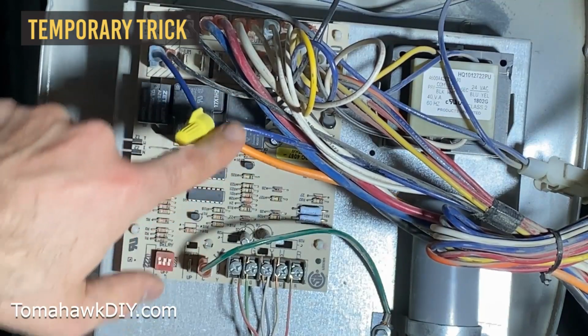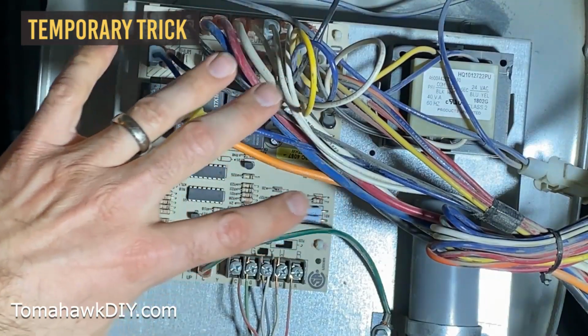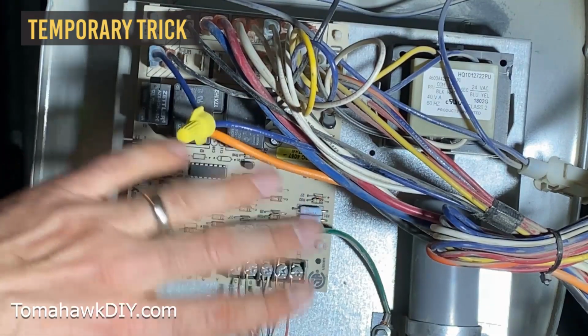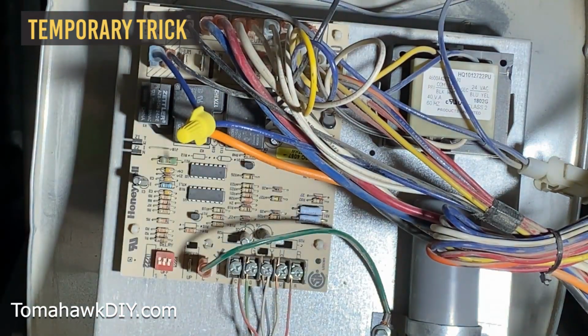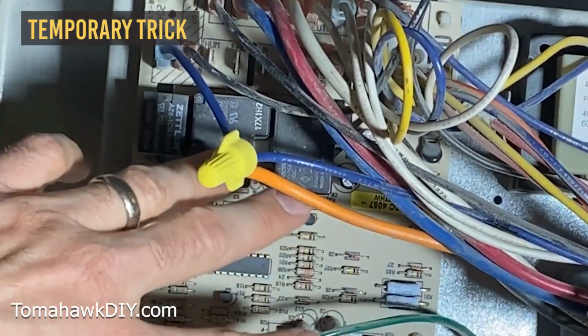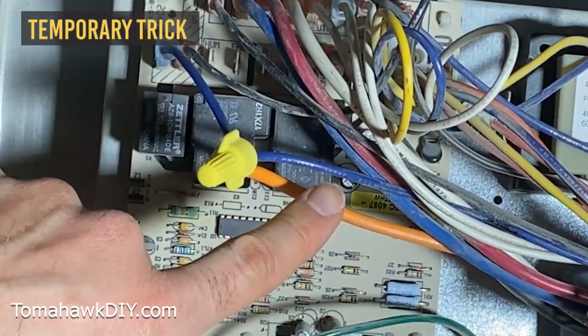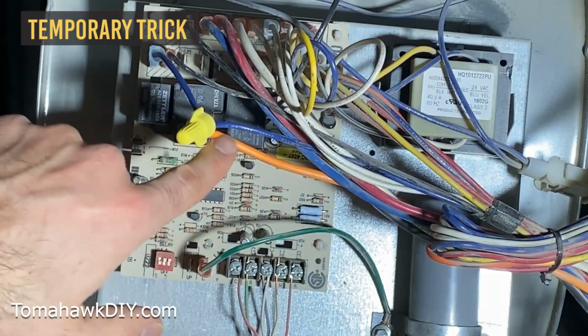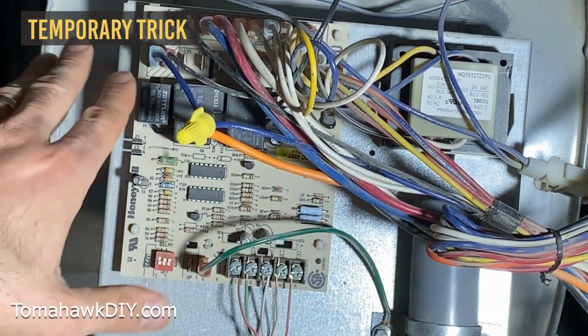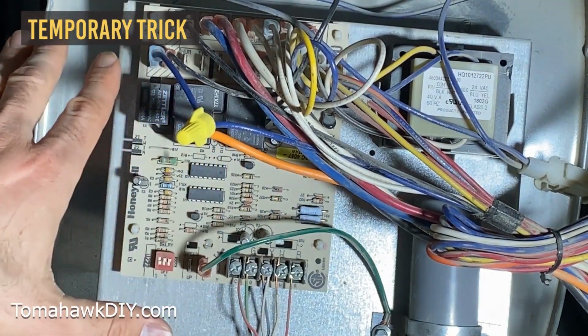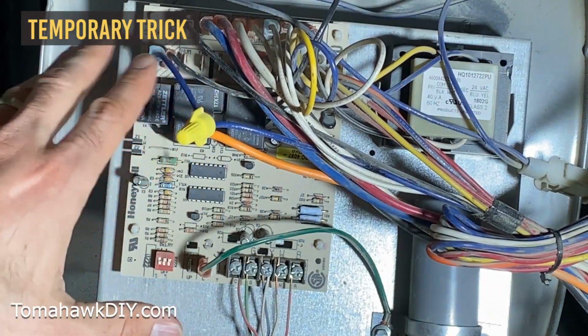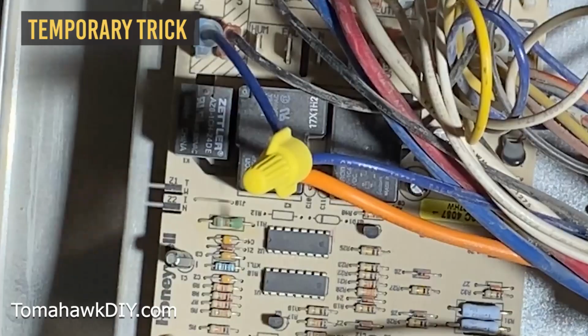He pointed out that sometimes if you have a problem like we had, the fan wouldn't blow, and so the furnace wouldn't run. It kept getting cold in the house because of that. The problem was with the circuit board, it appears, so we bypassed that part of the circuit board and plugged the fan in so it runs continuously, but it kept the air moving and allowed the furnace to kick on and fire up.